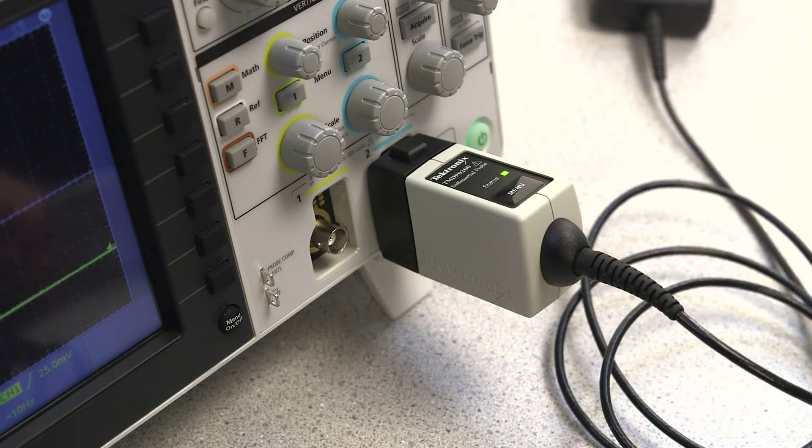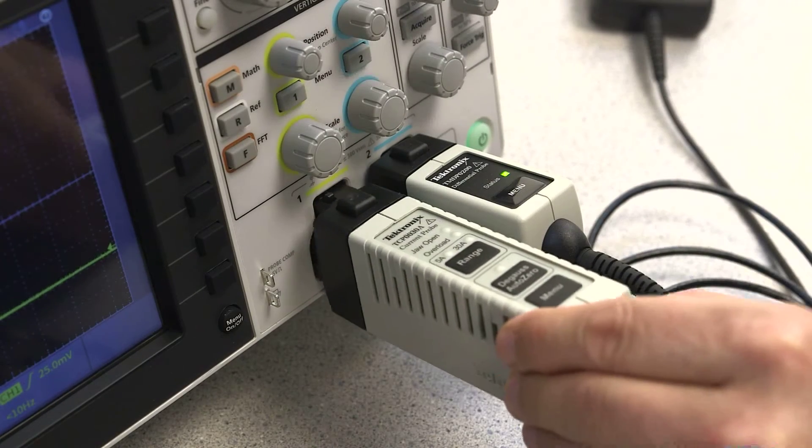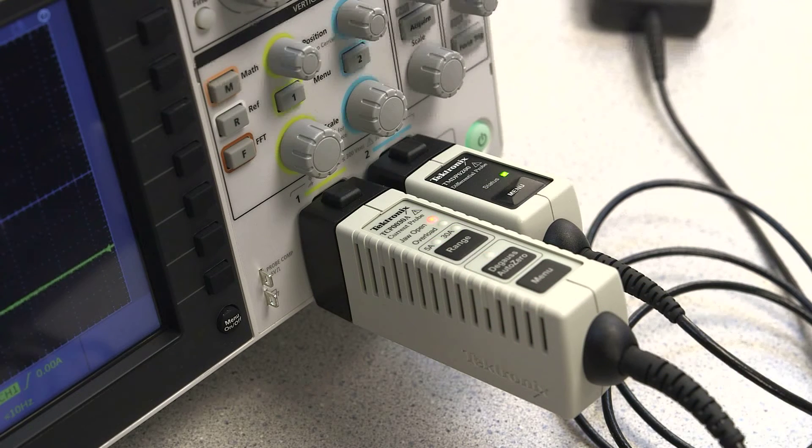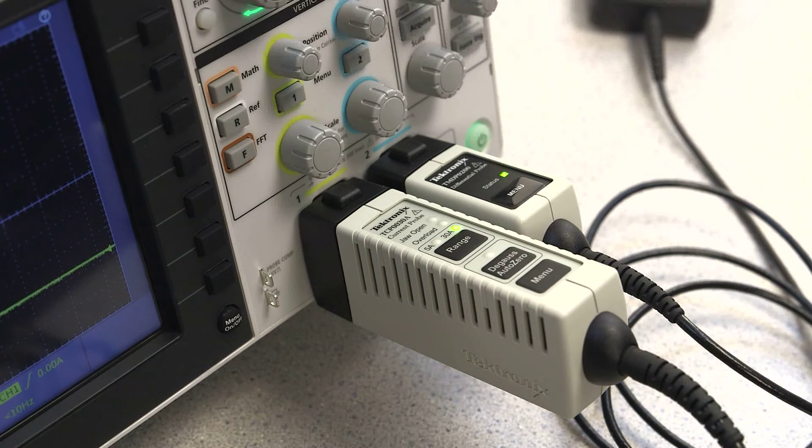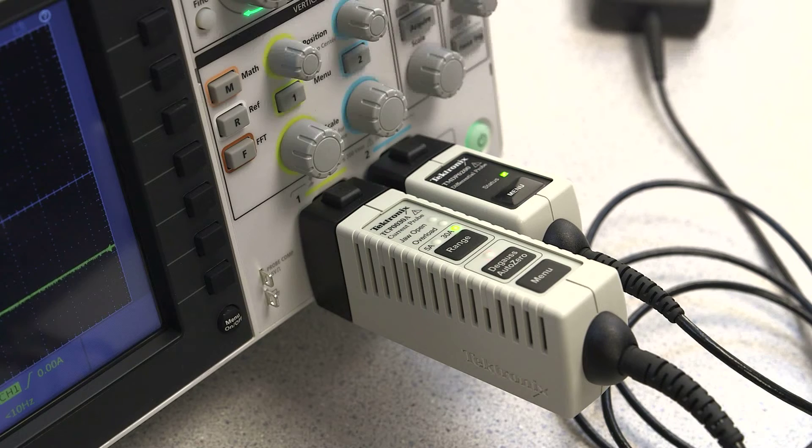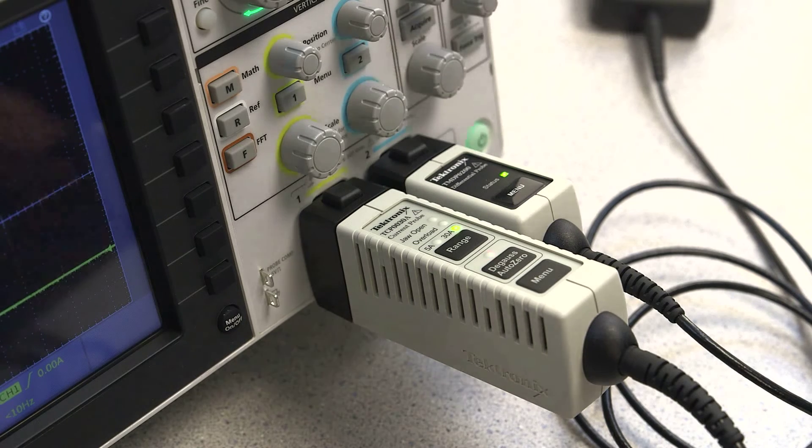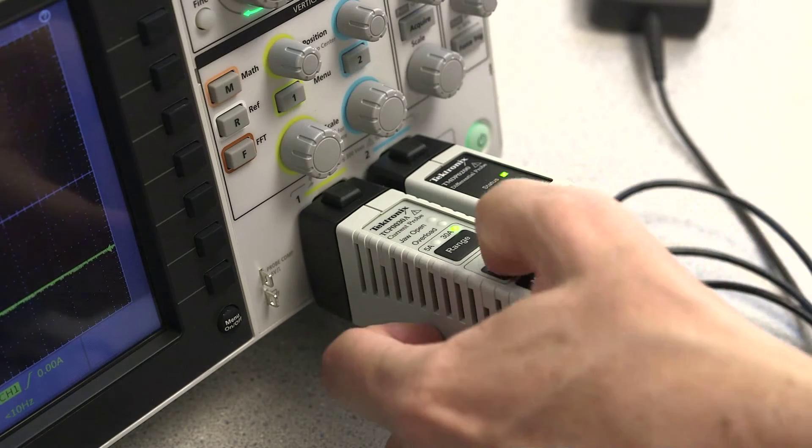The TekVPI probe interface supports standard BNC probes, but it also enables communication between the scope and the latest TekVPI current and differential voltage probes to simplify setups and cover a wide range of applications.